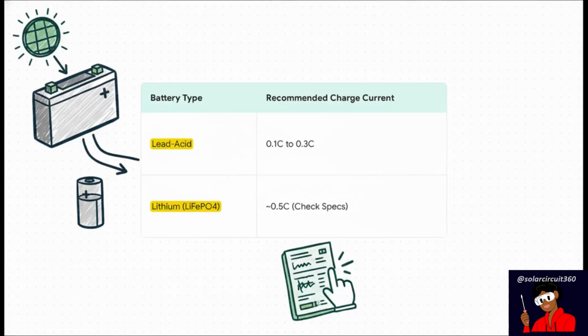So, what are the right numbers to aim for? Here are some really solid guidelines. For lead acid, you actually want to keep that charge current pretty gentle, somewhere between 10 to 30% of its capacity. That's the sweet spot for a long life. For lithium, like LiFePO4, it's often higher, maybe around that 0.5 C mark we talked about. But, and this is the most important part, you have to check the spec sheet from the manufacturer. That's your Bible. That is the final word.